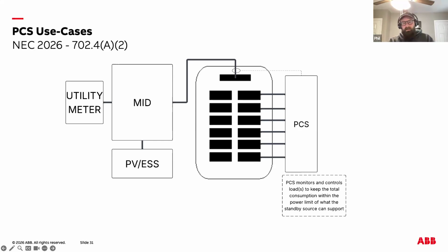In the illustrated setup, a load center is backed up by a PV ESS system that also includes a PCS. The PCS continuously monitors the loads on the backup panel and actively controls them, reducing, shedding, or sequencing as needed to ensure the total demand never exceeds what the standby source can safely deliver. This allows the system to remain code compliant without oversizing the ESS or restricting the homeowner to only a small subset of loads.